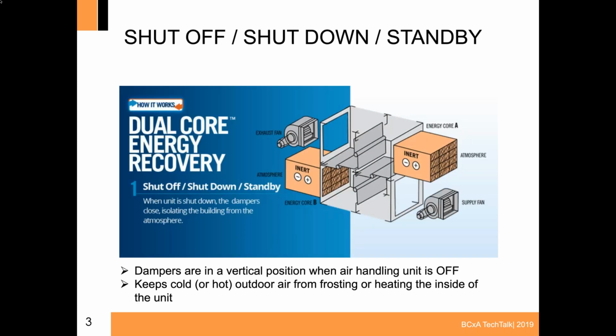So for the basics of the energy recovery core, when the system is shut down or in standby, for example when you're outside of your normal operating hours like a school is, the dampers, which you can see in the middle of the drawing, are in a vertical position. What this does is keep the cold outdoor conditions from penetrating into the air handling unit and being distributed into the school on startup.